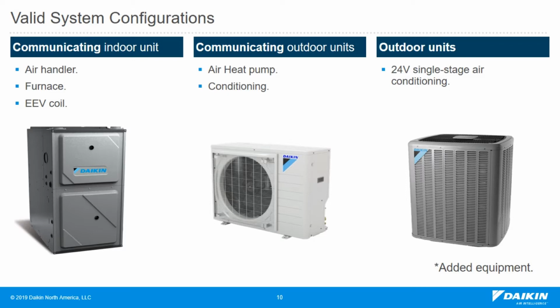To start, we're looking at the valid system configurations. Any communicating air handler, EEV coil on top of a blower, a furnace, communicating outdoor units. So any of the heat pumps or air conditioning that communicate, or we can do a non-communicating single stage condenser. And this is if we want full control of a communicating furnace, maybe zoning, and we just want the air conditioner to be basic, or we're doing an install where we'll do the furnace and the Daikin One and use the existing condenser and return in the future to do an outdoor inverter or two-speed unit.